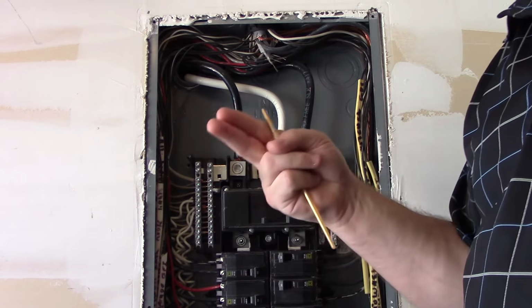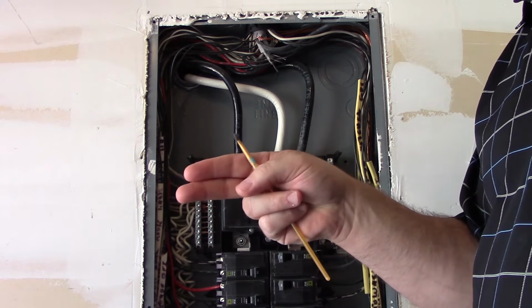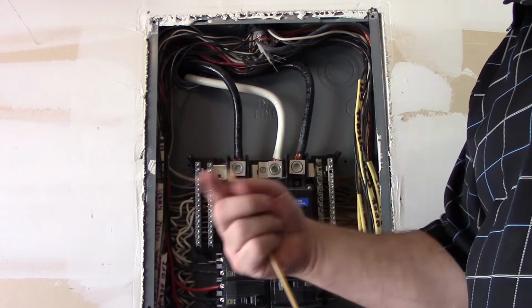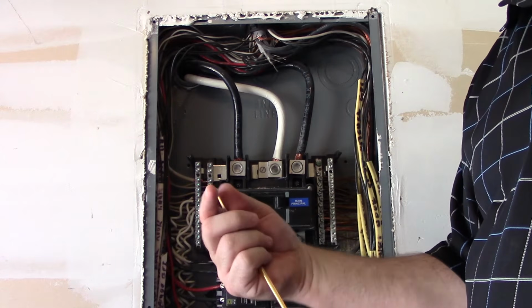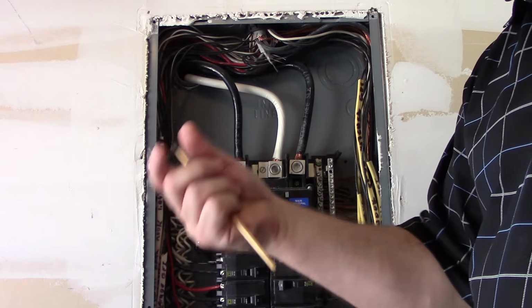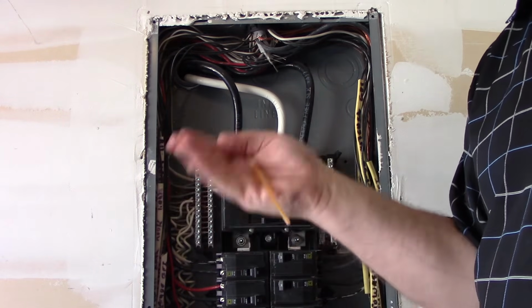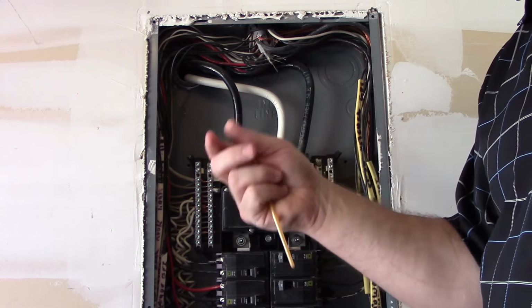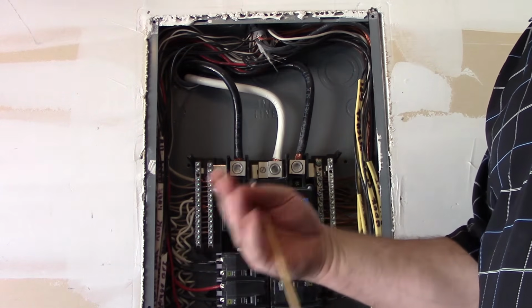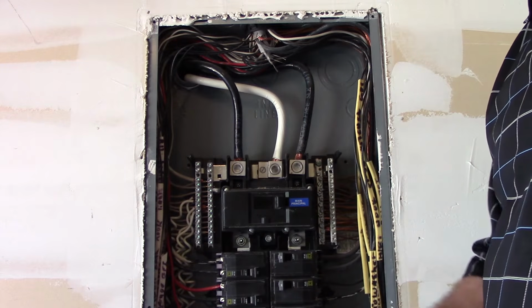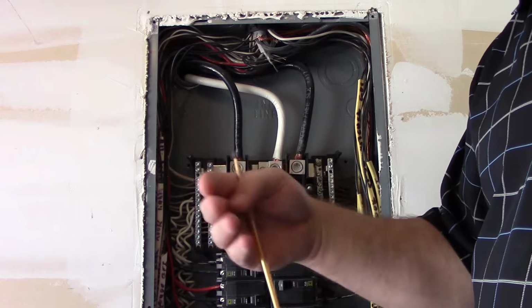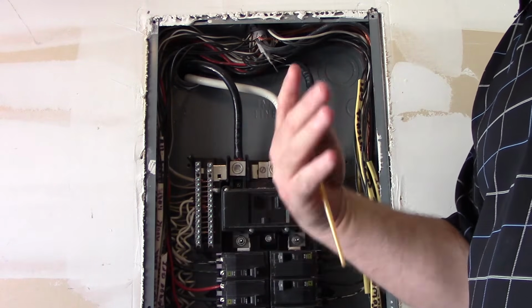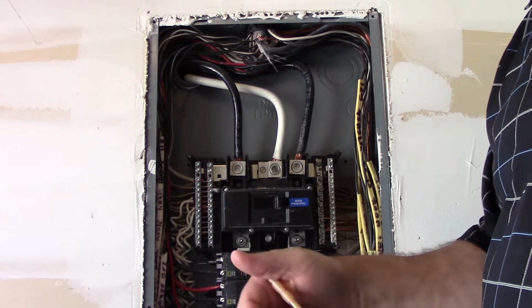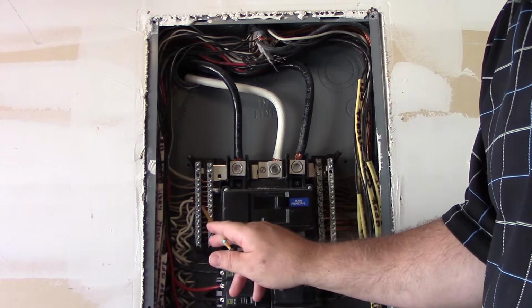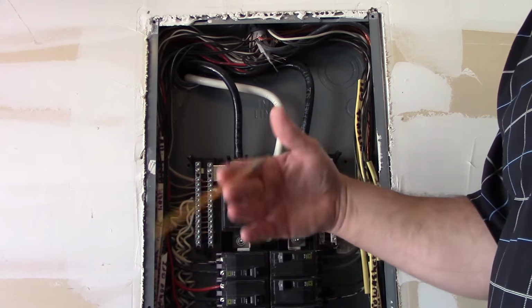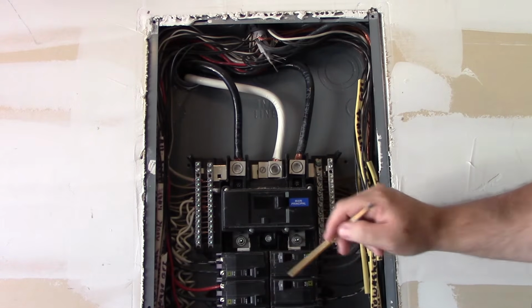The other aspect is that if you terminate two of them under the same lug and they were different sizes, then one wouldn't be making a good connection and would create an arc. It is a current-carrying conductor, so you're going to have current traveling through it, and if it's loose, you're going to create an arc. Arcs produce heat over time. It starts to melt down the insulation, raises its temperature, and can cause damage. It could come loose, and if it's a multi-wire branch circuit, you have an issue with the neutral coming loose. That could be a problem because you turn two 120 volt circuits into a 240 volt circuit, and that could damage things that are plugged into that multi-wire branch circuit. So we want to look and see if any of these are discolored, or if any of them are grayed out, because they could be on a multi-wire branch circuit and not properly aligned in the panel.